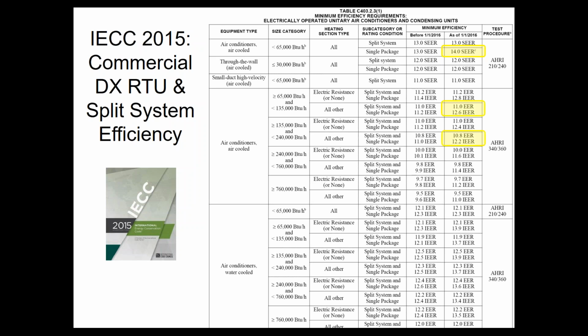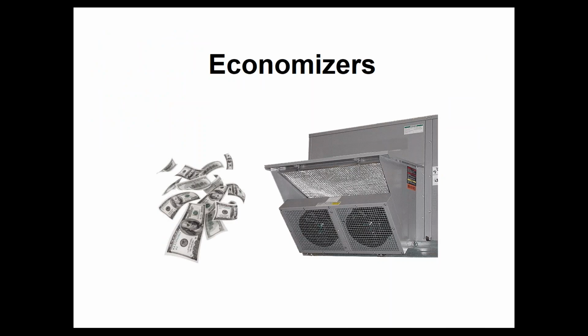And then for the bigger stuff, we go to that IEER. Now, right now, there's still an EER and IEER requirement. The EERs did not change from the 2012 book. The IEERs went up significantly. So they're basically telling you through the code, they're telling you full load is not very important, part load matters most. Right, so let's give you an example of a few of those there. And then this just keeps going on for different types of systems, and then for heat pumps, and then for boilers and chillers and so forth.